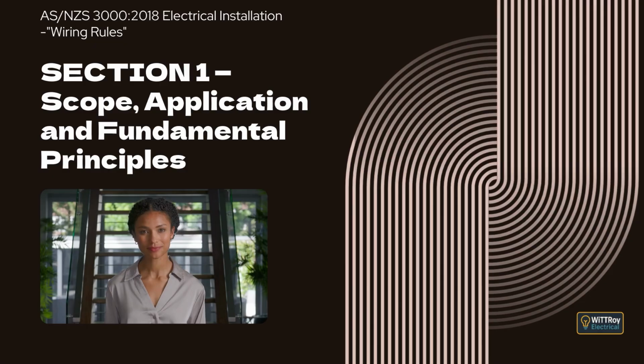We need to know the frequency, the maximum current available, and the possible short-circuit current. We also need to know what protection measures are present in the supply system, such as the main earthing system. And finally, we must understand any limits on equipment use, including harmonic levels and other characteristics that might affect the design. Clause 1.6.3 Maximum demand.